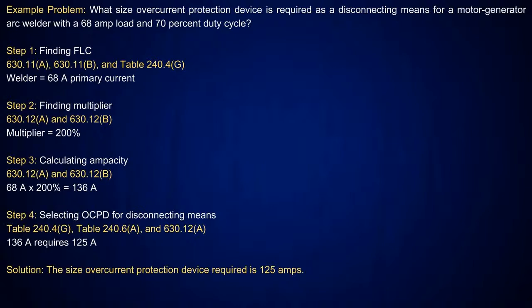Now, where the one we did before was non-motor, this is a motor generator type. All right. Now, we're just going to show you doing it without doing the conductor first. Because I can tell you can do the conductor, but I can already tell you which is going to be the largest. It's going to be taking the 200%. The reason we did that one before is to show you we took the conductor and got the amperage, took it at 200%, and it matched up to exactly when we dropped down. You see, that proves everything that we're teaching you.